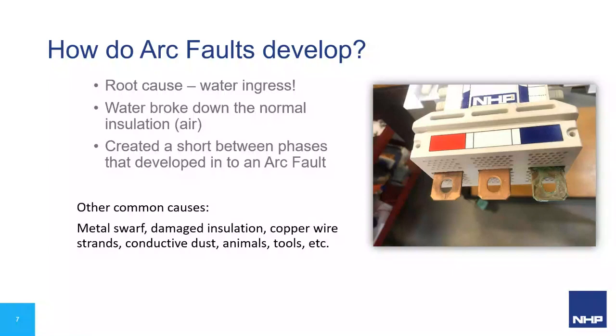So the water actually travelled within the cable because it did pass through some glands, and it made its way onto the conductors. Water and electricity, obviously, not a very good mix. We'll go into a little bit more detail a bit later, but you can imagine that that water is what really started that flow of current. One thing I'll point to, that we'll come back to, is this was a relatively rare case where there was nobody physically at the switchboard at the time of the arc fault event. This happened with a closed door, in a switch room, all on its own, and it's only when the lights went out and the circuit breaker tripped that people went to investigate what had happened.